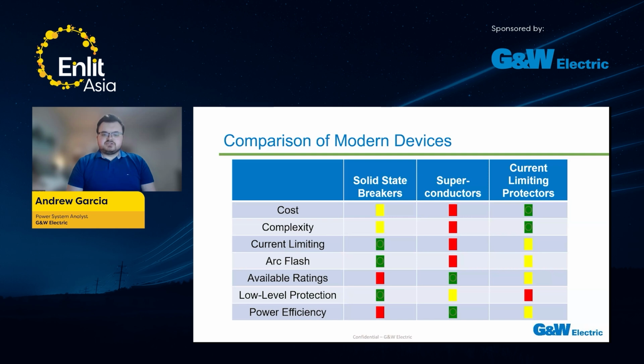In terms of power efficiency, once again, superconductors are the best. You can't beat near zero resistance. Current limiting protectors come in second, as they're just a bus bar under normal operation. And solid state breakers come in last because they're electronic, and therefore there's a very slight dip in power efficiency when using those devices.